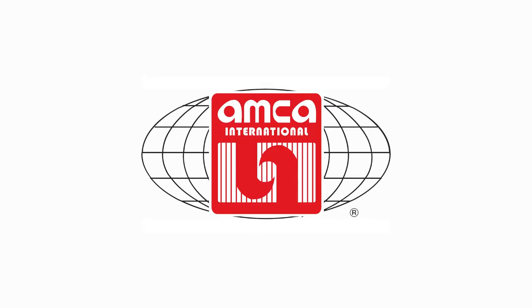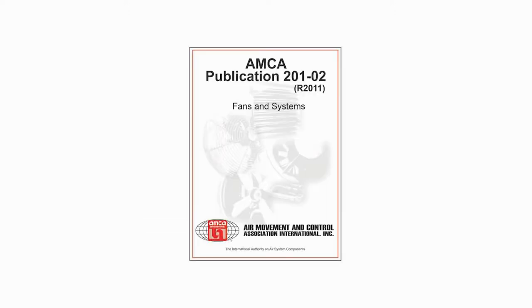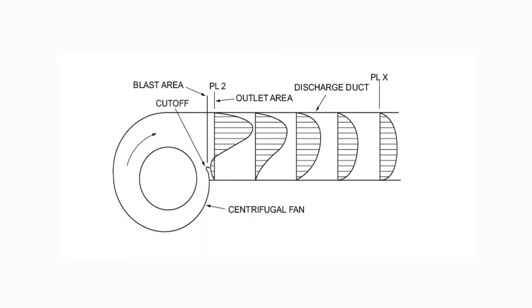AMCA, the Air Movement and Control Association, establishes test standards for fans and a certified rating program that ensures uniformity in fan testing. AMCA Standard 201 shows why discharge duct length is important. This diagram, taken from AMCA 201, shows the velocity profile at the discharge of a typical blower. You can see that, as the air immediately leaves the blower, the velocity of the air in the duct varies widely. And as the air travels along the duct, it evens out. The velocity profile at the end of the duct is known as a fully developed flow, and provides the opportunity for the lowest pressure loss as the duct system changes directions.